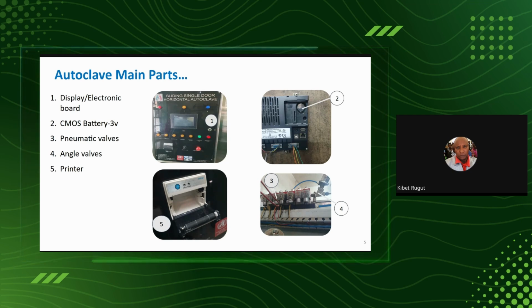So there is an electronic display board, and it usually has all the buttons for start, stop, and all the cycles that we have seen in the previous slide. Then it also gives other displays that you may not have mentioned: the temperature, the pressure in the boiler and also in the sterilization chamber, and also the vacuum power that you are using to evacuate the chamber.